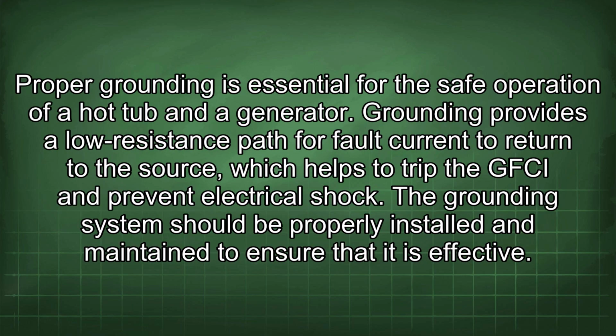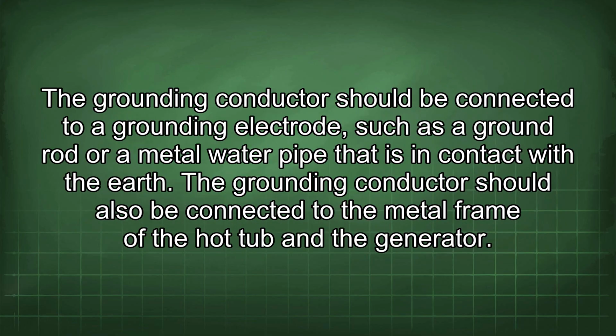Proper grounding is essential for the safe operation of a hot tub and a generator. Grounding provides a low resistance path for fault current to return to the source, which helps to trip the GFCI and prevent electrical shock. The grounding system should be properly installed and maintained to ensure that it is effective. The grounding conductor should be connected to a grounding electrode, such as a ground rod or a metal water pipe that is in contact with the earth. The grounding conductor should also be connected to the metal frame of the hot tub and the generator.